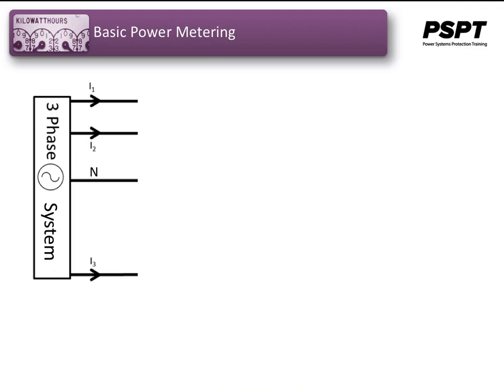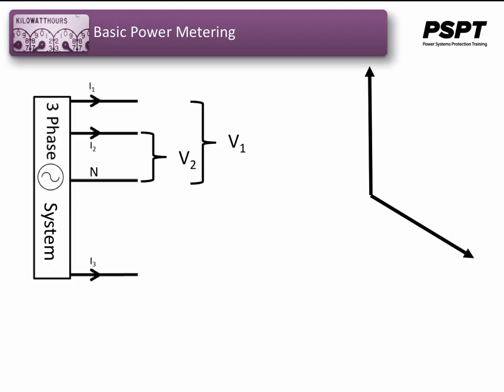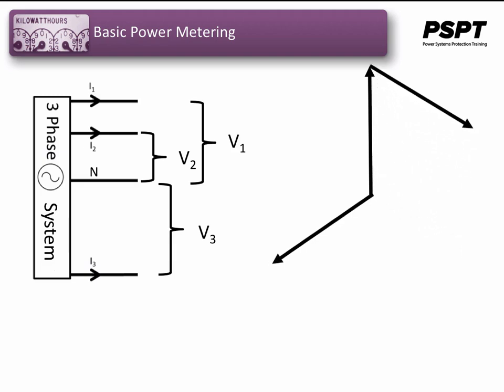If we look at the voltages here, if we look at voltage V1, the phasor would look something like this. Then voltage V2, or V2 to neutral, would be 120 degrees lagging that voltage and look somewhat like this. And voltage 3 would look something like this. When the voltages are added together, because they're equal and 120 degrees apart, the vector sum, or phasor sum, of the voltages will add to 0. And for the next stage in metering a three-phase system, we'll use this identity where the voltages of a three-phase system will add to 0 in order to make reductions in the number of elements used in a meter.